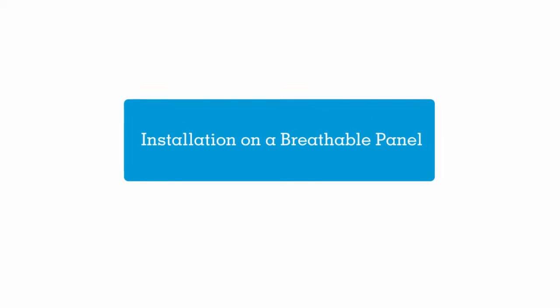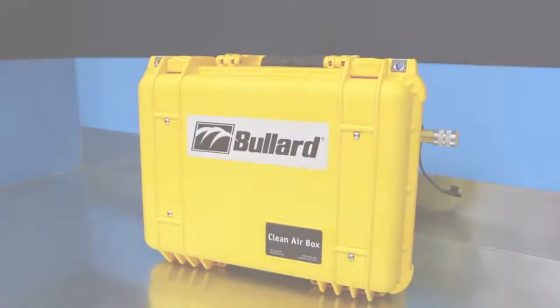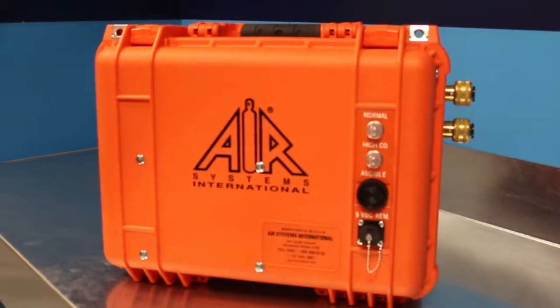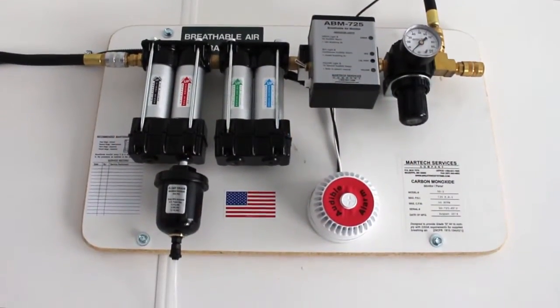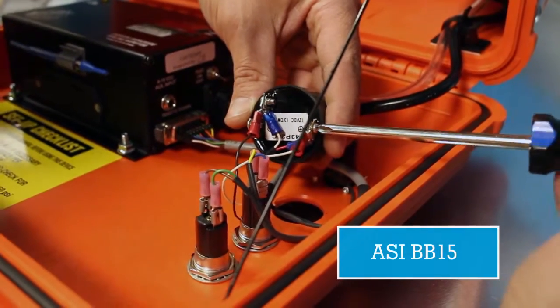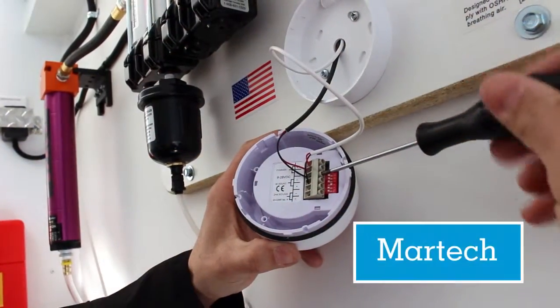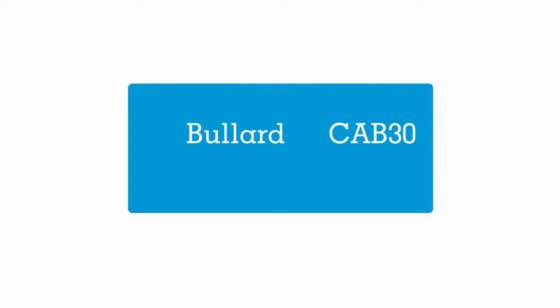Interfacing the RAS with breathable panels can be as simple as a plug or inserting two wires into a terminal strip. For the Bullard Cab 15, ASI-BB15, and Martech, the RAS leads are manually installed — simply connect the wires to the terminal. For the Bullard Cab 30, ASI-BB30, and larger units, a serial-style connector is available.